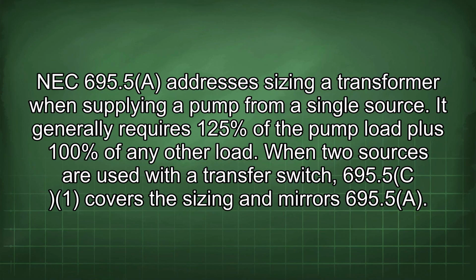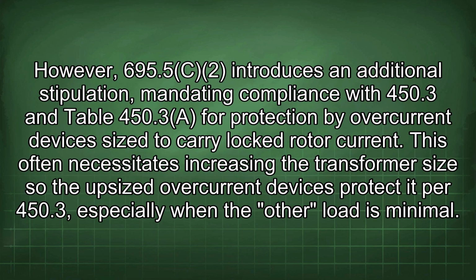NEC 695.5 addresses sizing a transformer when supplying a pump from a single source. It generally requires 125% of the pump load plus 100% of any other load. When two sources are used with a transfer switch, 695.5 C1 covers the sizing and mirrors 695.5A.